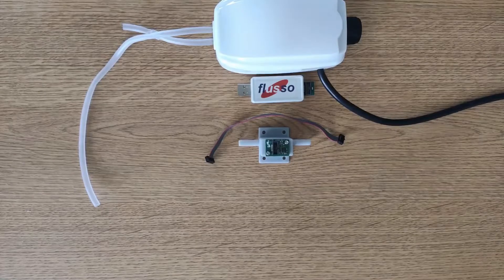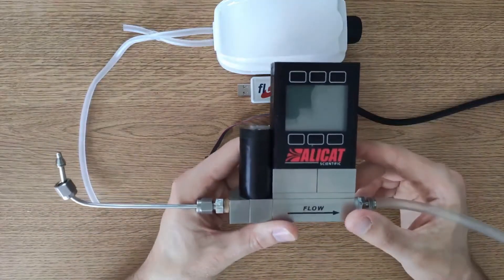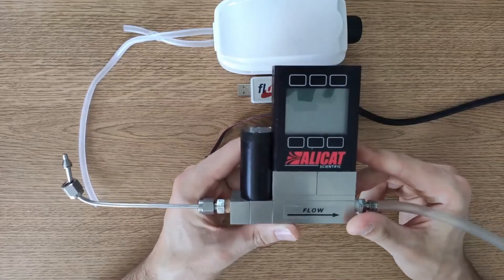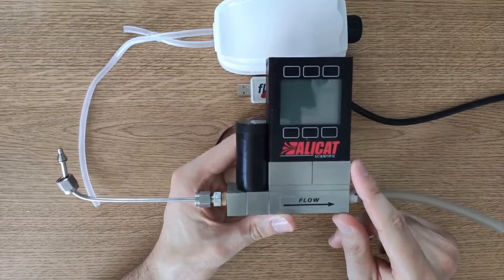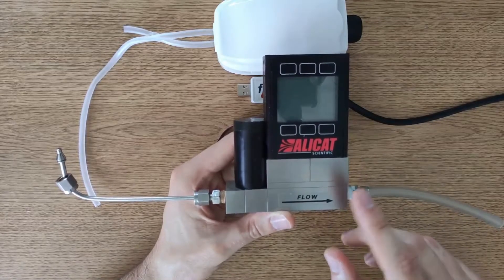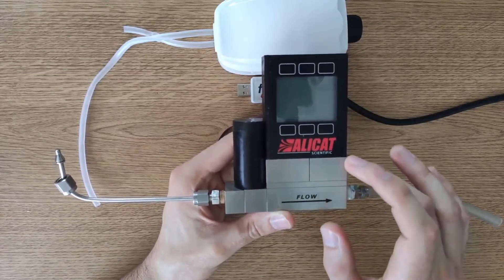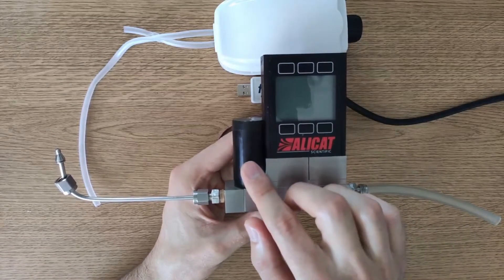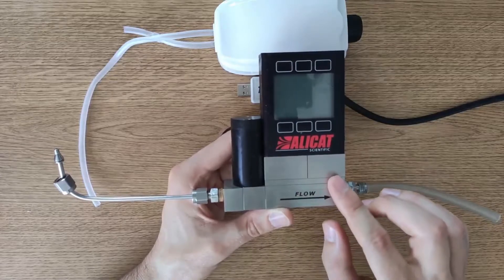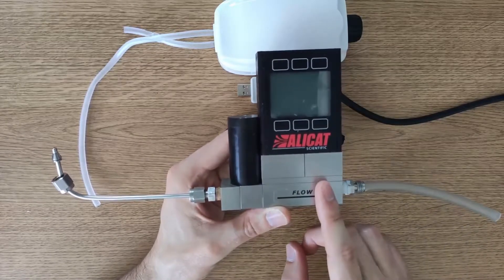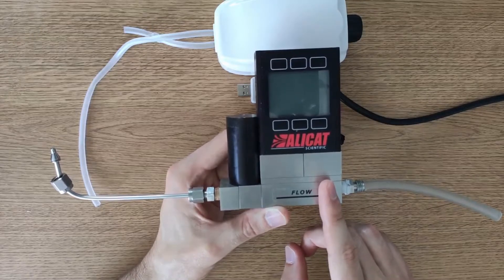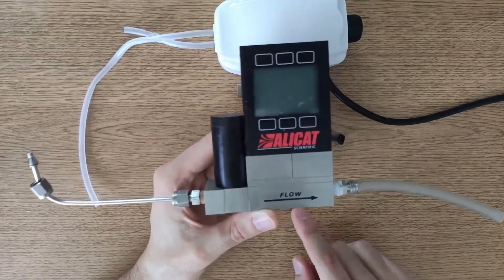You're also going to need a flow controller and a reference flow meter. Something like this Alicat mass flow controller is a good solution for both of these things. It incorporates a reference flow meter and also it's got a proportional valve which means it can control the flow very precisely which is useful for calibration. This is a 500 SCCM mass flow controller and of course that matches up nicely with the 500 SCCM fixture that I have here.